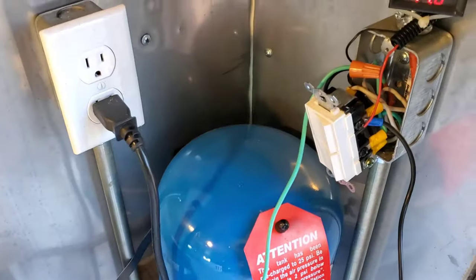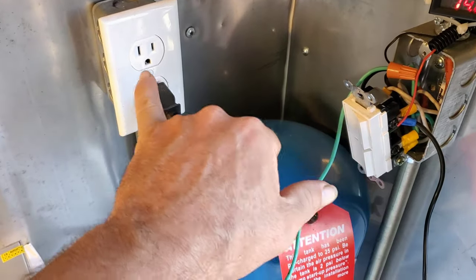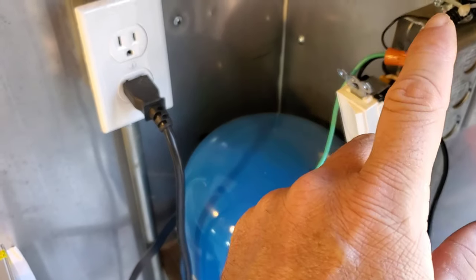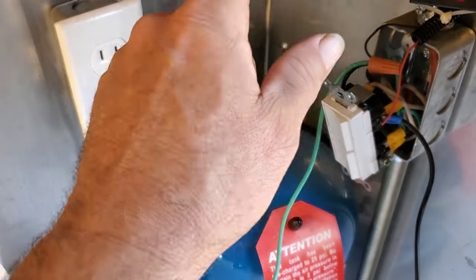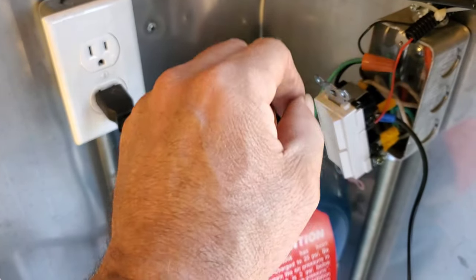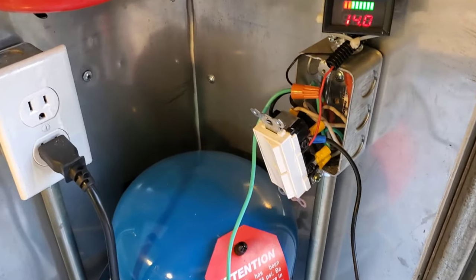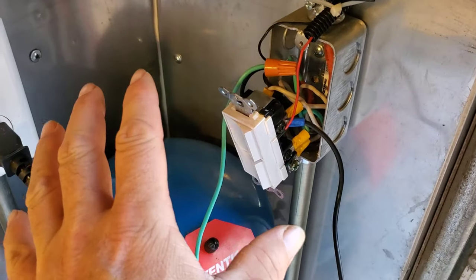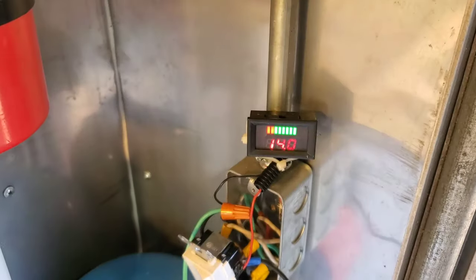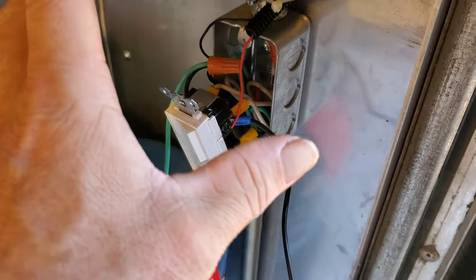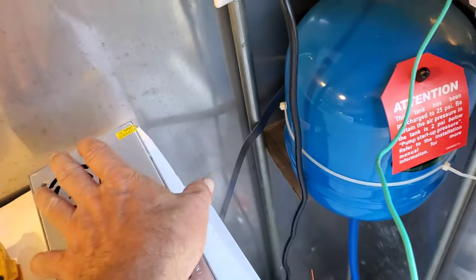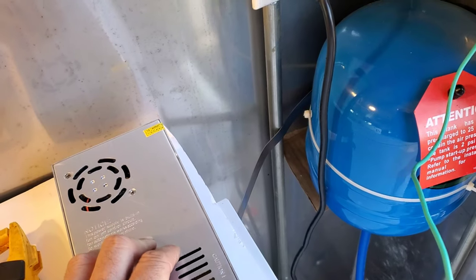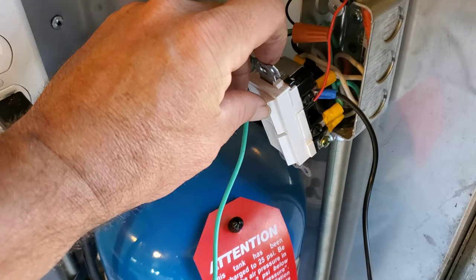All right, so quick tip: you are not allowed to have 12 volt and 110 in the same box. Say for instance you had two light switches, you can't have a 12 volt light switch and 110 light switch in the same box, they have to be in separate boxes. And again, the only reason I've got this out, this is temporary. I'm gonna stub off of it like I did here with the EMT and create, raise this up so it has good airflow in the back and good ventilation. But let's give it a test.